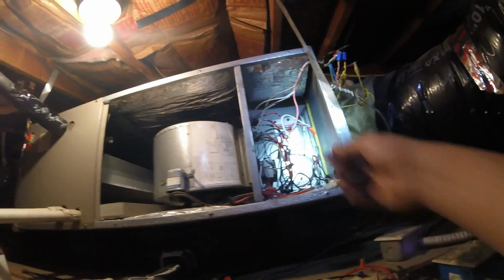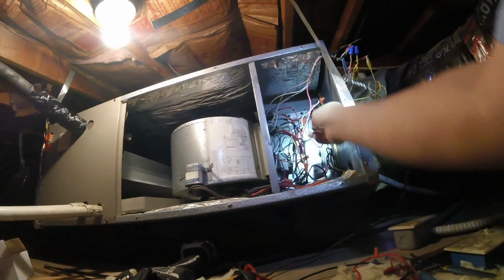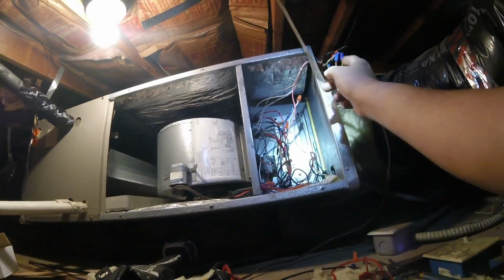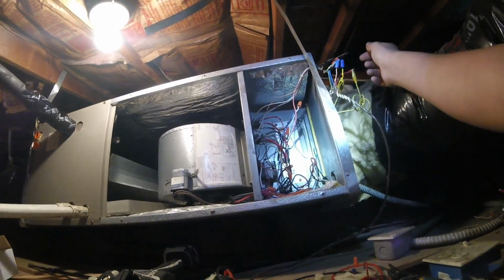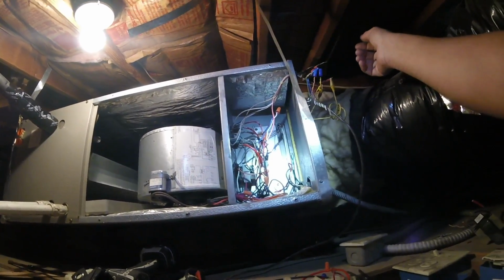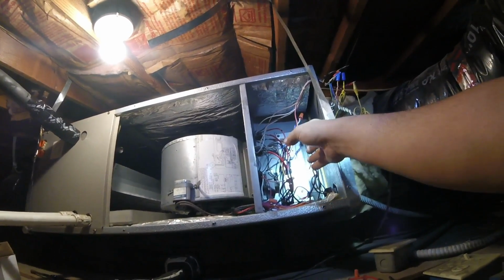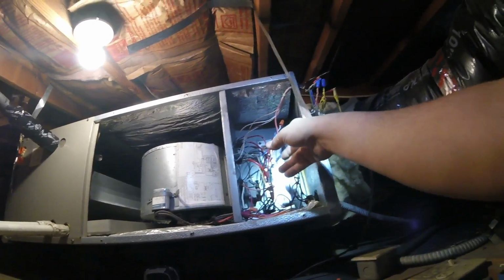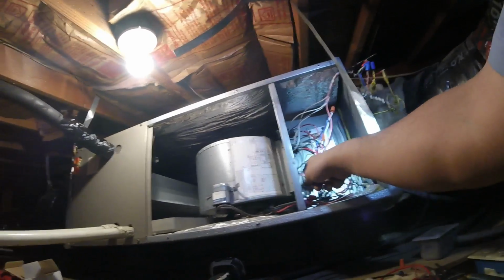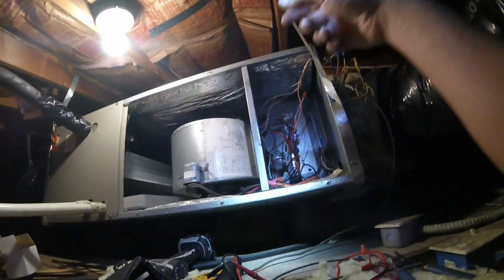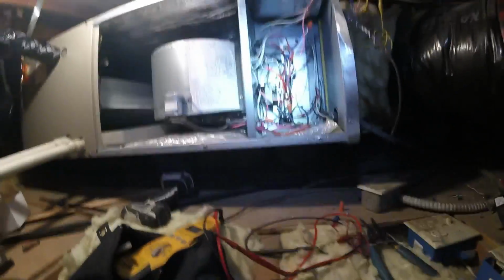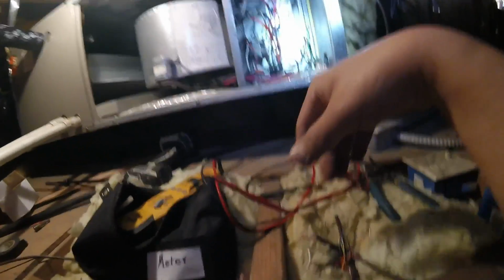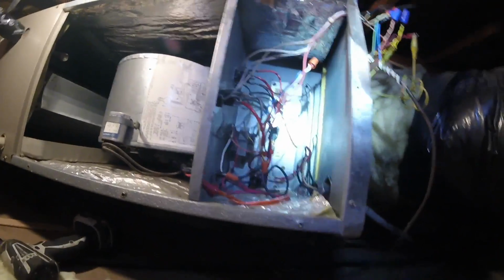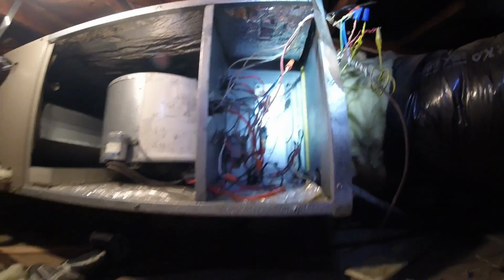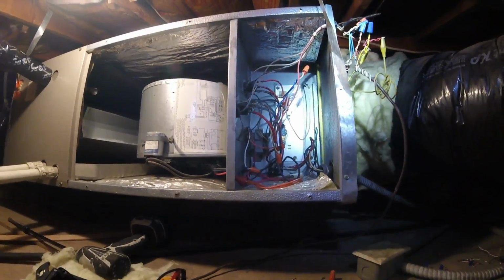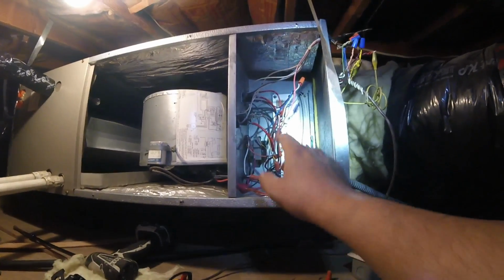Finally! Alright, this is what I did. It didn't have any ground from the transformer. It went straight into the R for the thermostat and for the condenser, and it wasn't connected to any ground, the transformer, the secondary side. Also, the transformer that I had in my truck was bad. That's what happens when you put an old, broken, used, faulty part back into this new box. You sometimes grab it by mistake and confuse the heck out of yourself. So that's it. Put the new transformer.